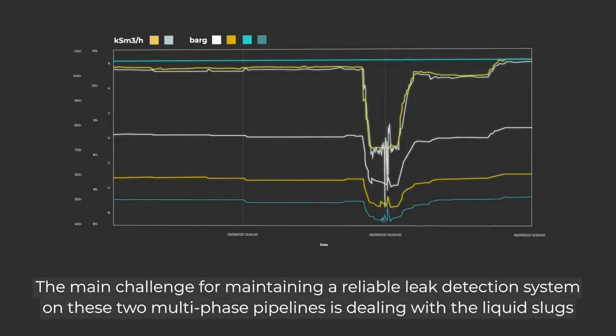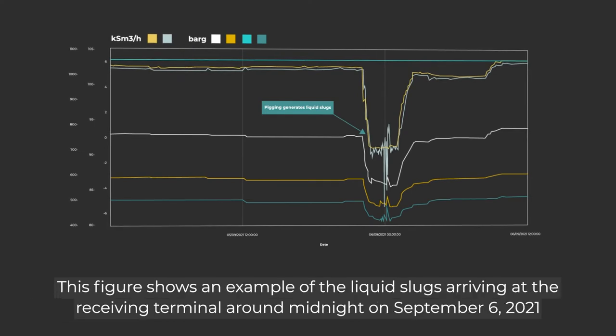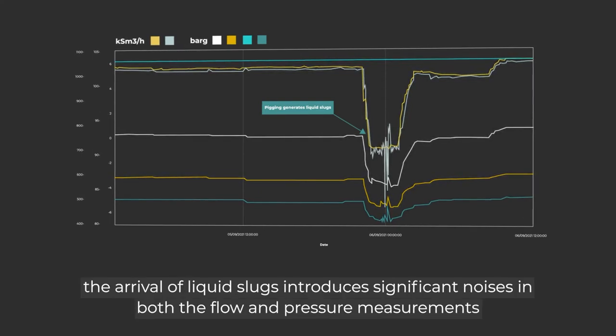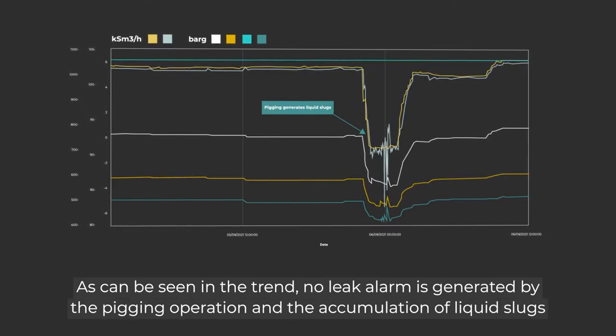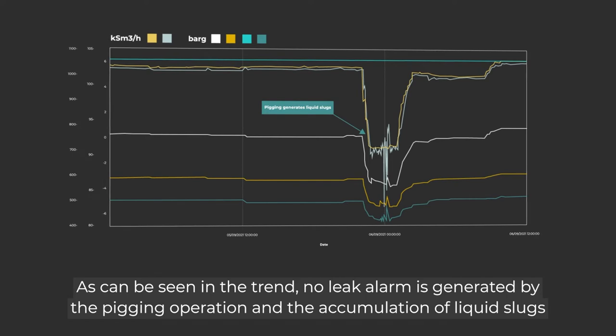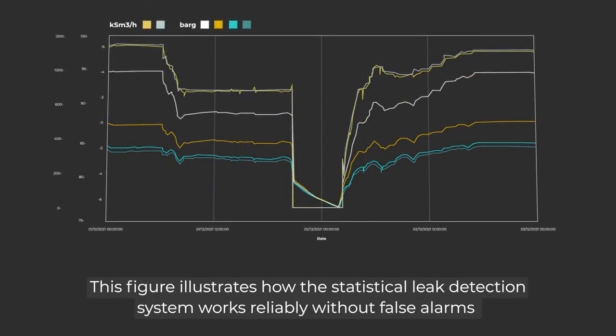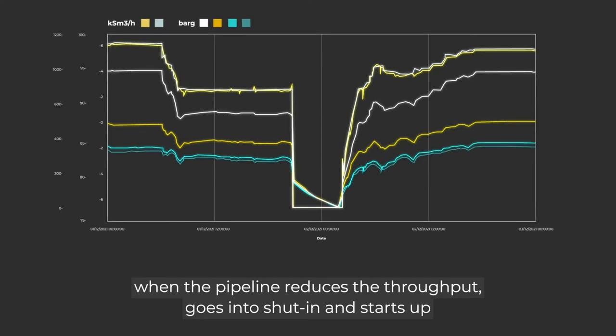The main challenge for maintaining a reliable leak detection system on these pipelines is dealing with liquid slugs. This figure shows an example of liquid slugs arriving at the receiving terminal around midnight on September 6, 2021. The arrival of liquid slugs introduces significant noise in both flow and pressure measurements. As can be seen in the trend, no leak alarm is generated by the pigging operation and accumulation of liquid slugs. This figure illustrates how the statistical leak detection system works reliably without false alarms when the pipeline reduces throughput, goes into shut-in, and starts up.